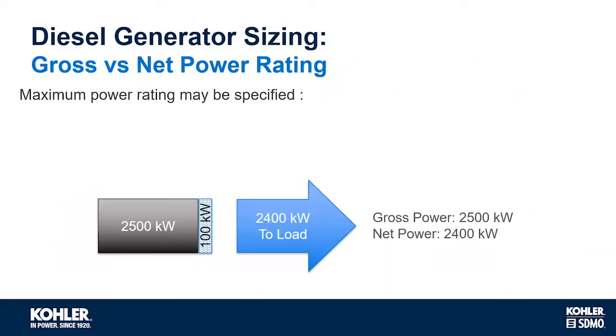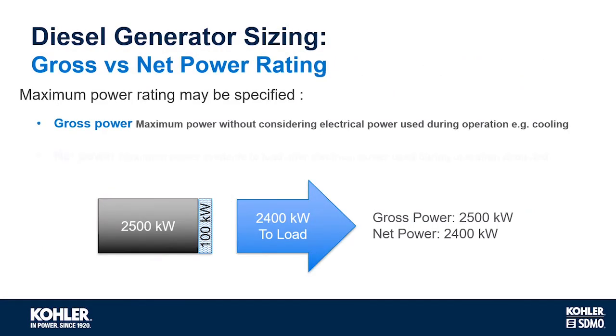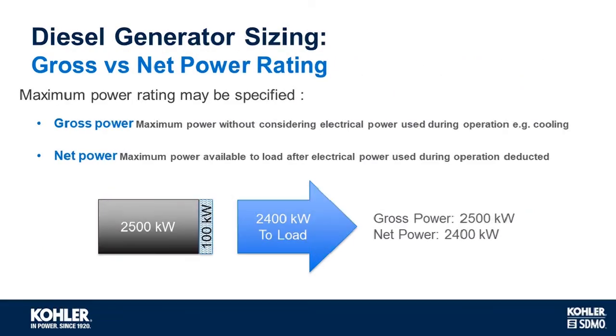Just briefly, let's talk about gross versus net power. An important point, because not all manufacturers include them in their advertised power outputs. The difference between the two is the parasitic loads, the main one being the cooling system for the engine, and to a lesser extent, any power used for ancillaries whilst a genset is running. So, typically, a 2,500 kilowatt genset has around 100 kilowatts of parasitic load, which means 2,400 kilowatts is available to support the load. Not taking this into account can result in the generator system being undersized.